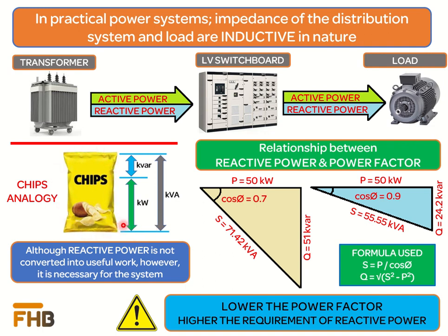Reactive power will remain in the system. It is important to understand the relationship between power factor and reactive power. Consider a system with a connected load of 50 kilowatts and a measured power factor of 0.7 — the reactive power is 51 kilovar. If we improve the power factor to 0.9 with the same 50 kilowatt load, the reactive power reduces to 24.2 kilovar. This shows that reactive power reduces with an increase in power factor — the lower the power factor, the higher the demand for reactive power.